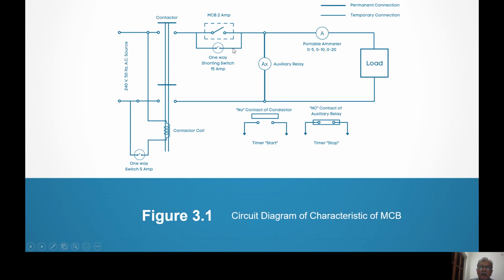In parallel to the MCB, we are keeping a 15 ampere switch so that while we are adjusting the current, the MCB does not trip. We will adjust the current exactly as we like. During that time, the MCB will not trip because current is not passing through it. But once we are sure that we have passed so much current, we will make this switch off and the MCB on, and then current will start passing. And after a predetermined time, the MCB will trip.